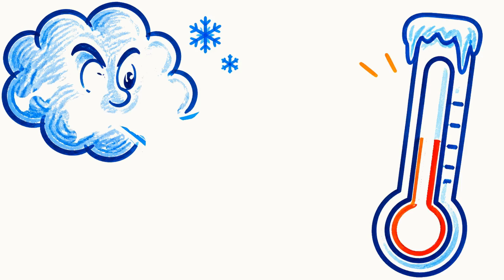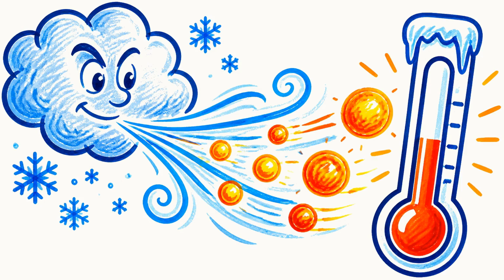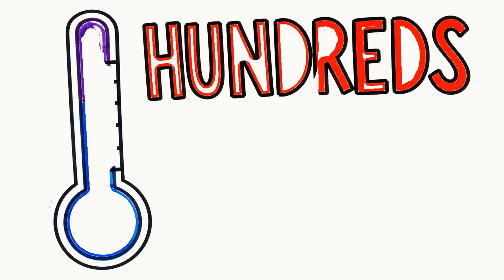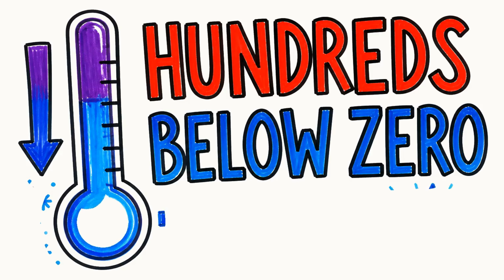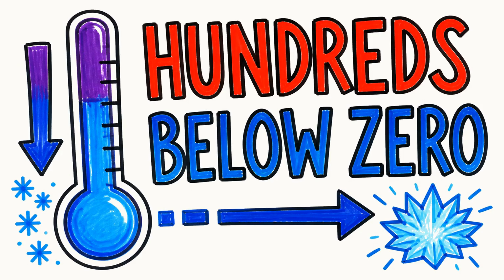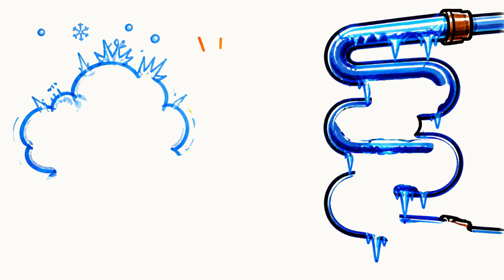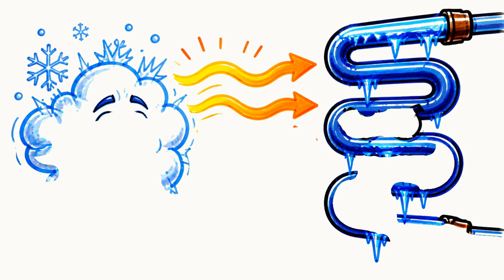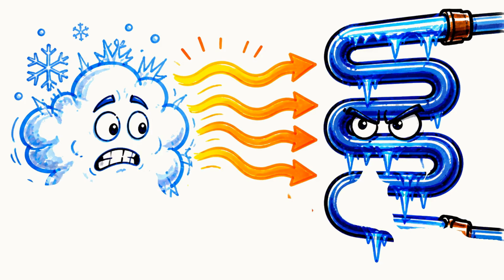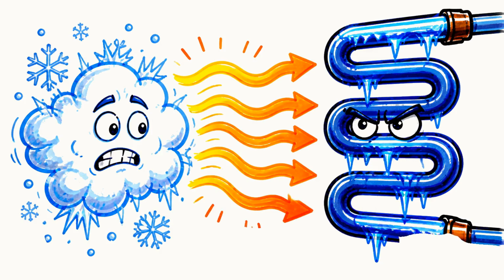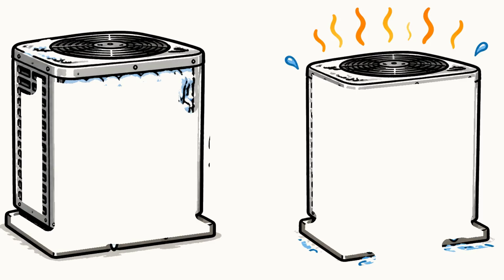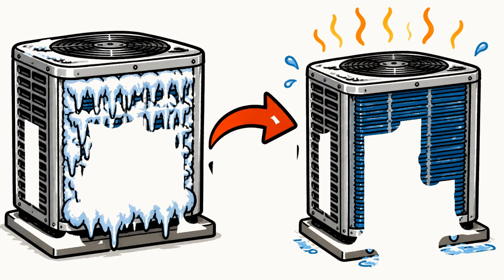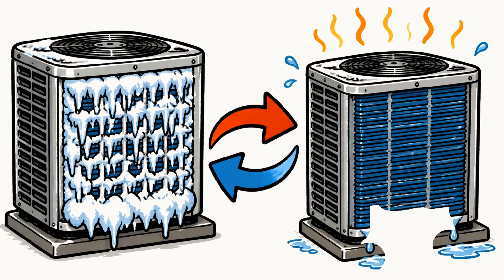The answer is that even freezing air still holds heat energy. Air is not truly empty of heat until you get down near hundreds of degrees below zero. The refrigerant inside a heat pump runs far colder than the outdoor air, colder than the frost itself, so heat still flows out of that cold air and into the even colder refrigerant. When it gets cold and damp enough, frost cakes onto the outdoor coil, so the unit briefly runs itself backwards to melt the ice off.